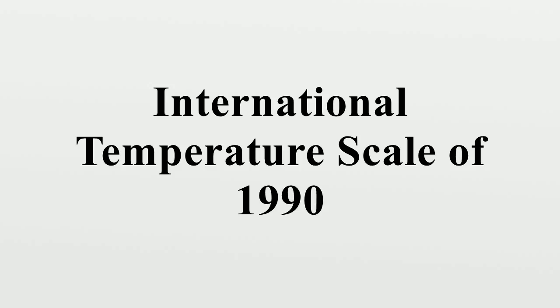ITS-90 is designed to represent the thermodynamic temperature scale as closely as possible throughout its range. Many different thermometer designs are required to cover the entire range. These include helium vapor pressure thermometers, helium gas thermometers, standard platinum resistance thermometers, and monochromatic radiation thermometers.